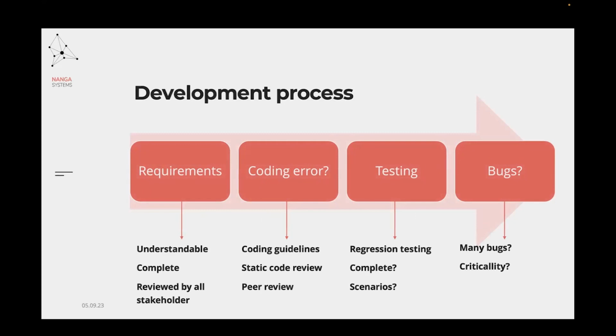We talked about the development process and how it is required for Class B and Class C devices. This is one of the reasons why it's important to define the software safety classification early in the game. It is not required for Class A devices to have a documented development process, but with a good and documented development process, we can already have a kind of risk control measure through the processes that we have applied. The main areas are requirements, development or coding errors in this case, testing, and bug management or defect management.